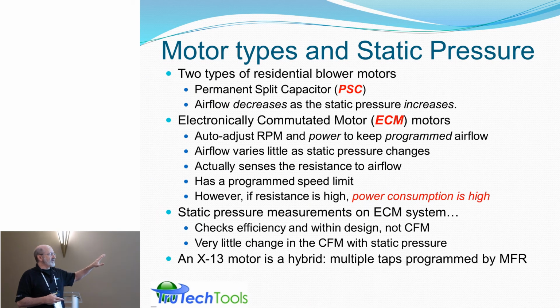So two types of residential blower motors. Again, we're focusing on residential, the PSC motor and the ECM. I'm sure you're all familiar with that because that's a long ago change, but they still have to deal with existing equipment in the field. The ECM motor adjusts itself to keep the programmed airflow.